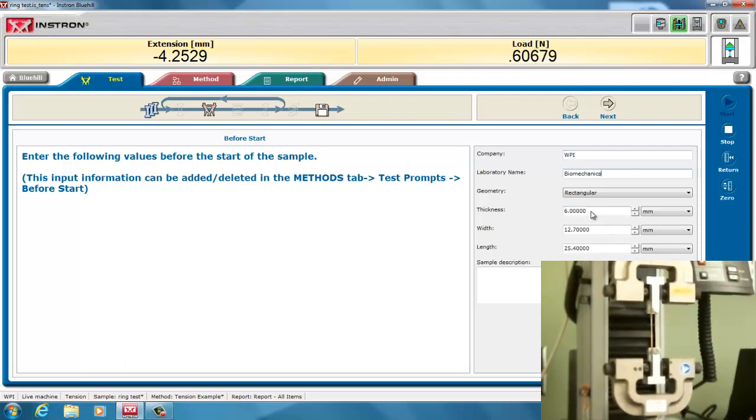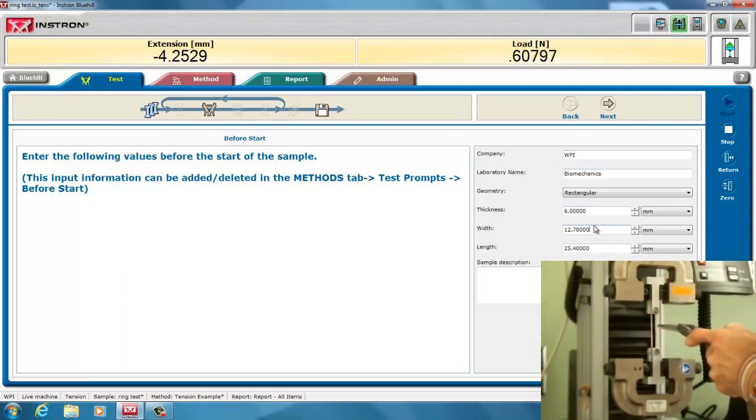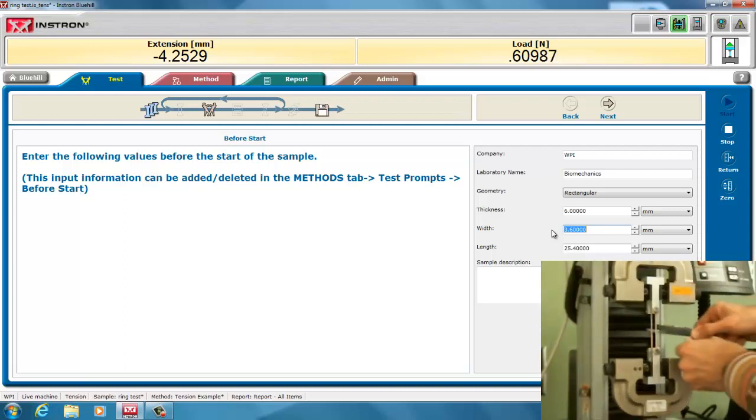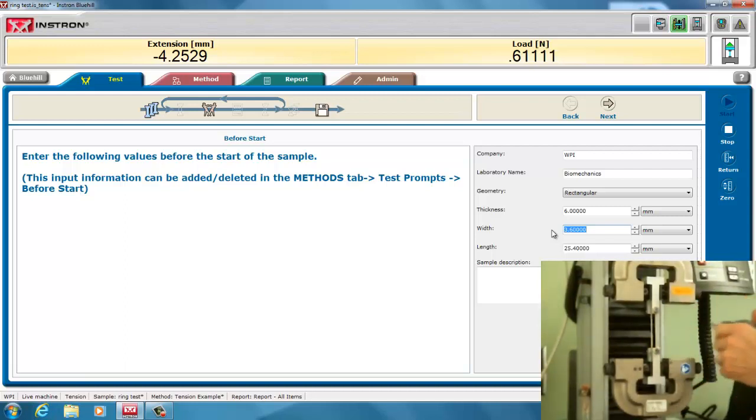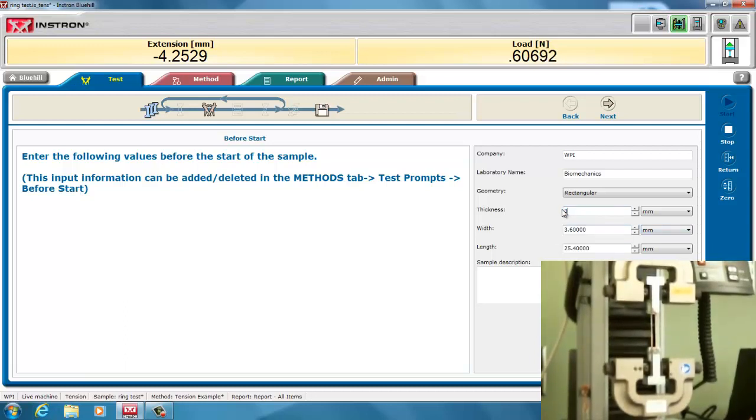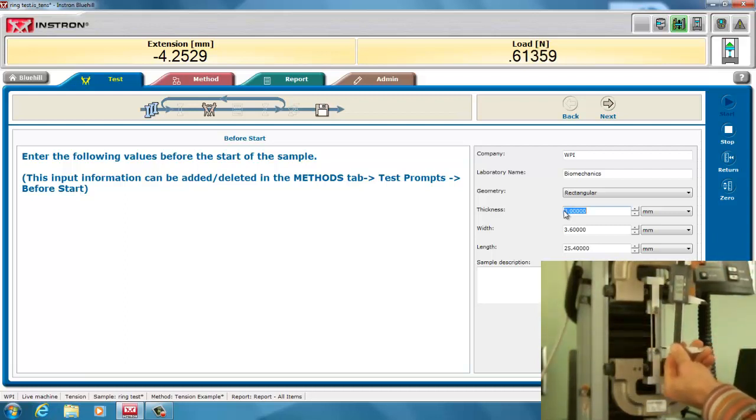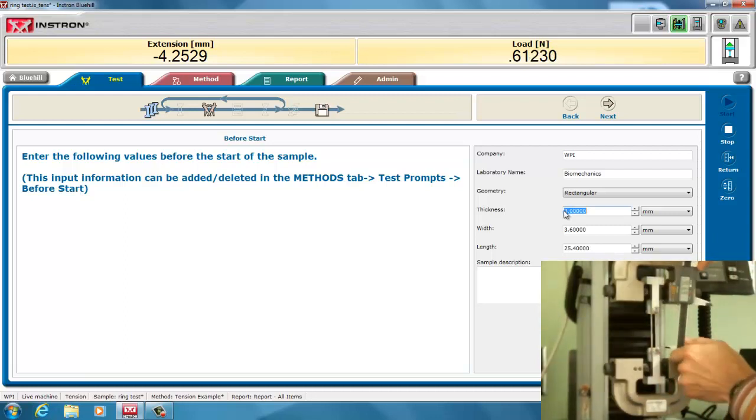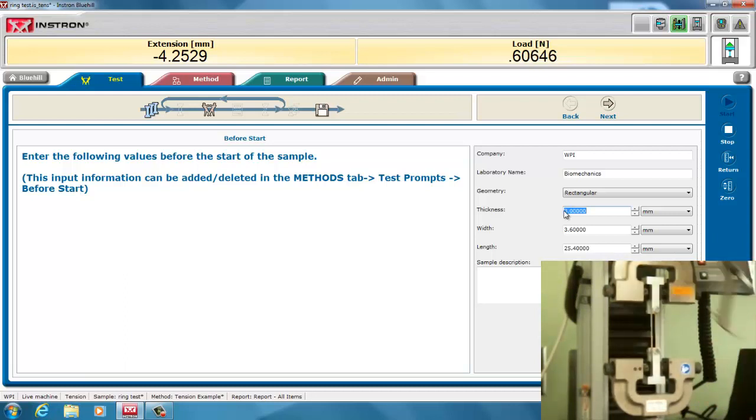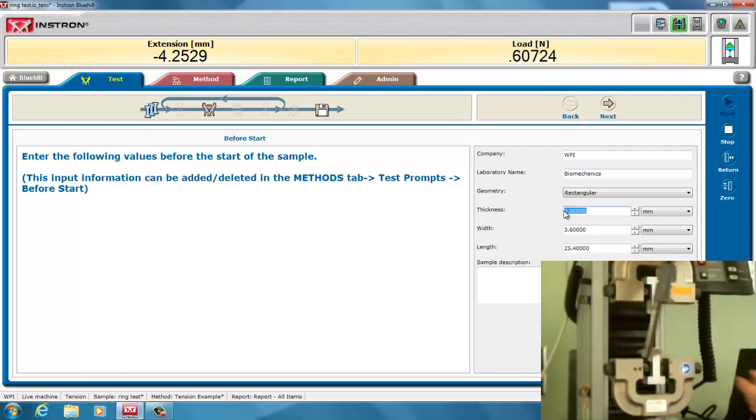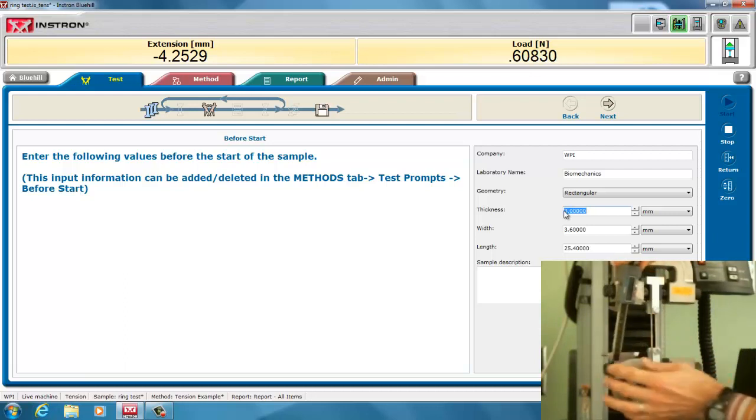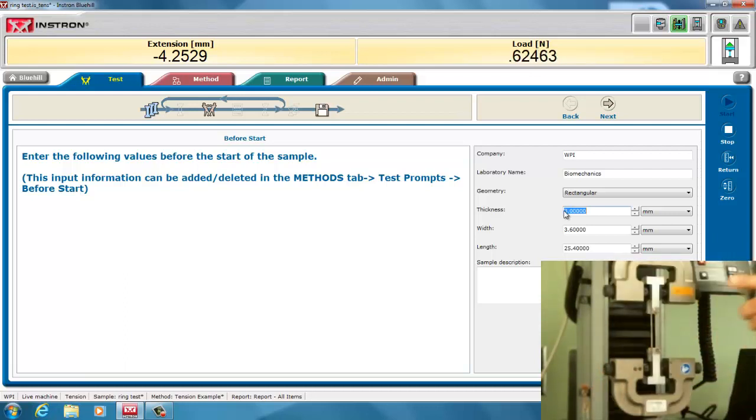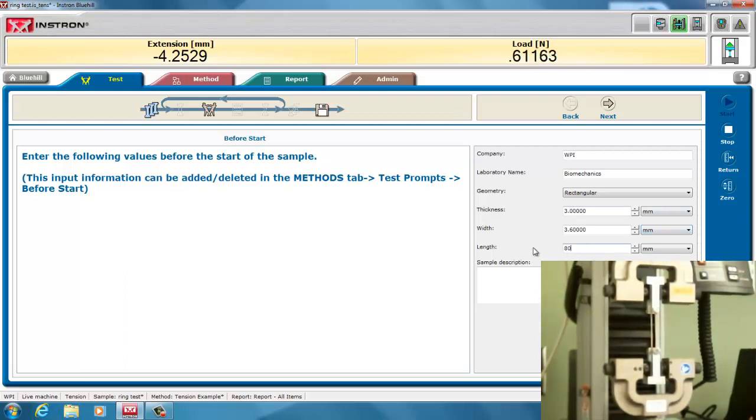So as I said, I'll take the width of the sample, and then the thickness, which was 1.5, but instead of putting 1.5, I'll put 3 so that it calculates it correctly. So under a tare load, I can measure the length here from the bottom of the grip to the top of the grip. Now this measurement is from the outer diameter of the two screws. Not between the grips, but between the screws that are in there.